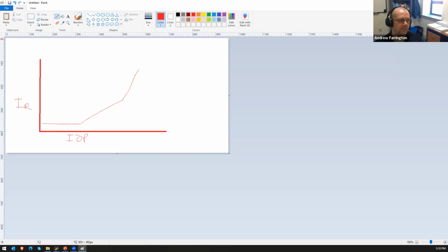Did that answer more or less what you were looking for, Paul? Yeah, it's just getting a bunch of points so that you're right below the curve and right above the curve. Oh, I see what you're saying. Yeah, to make sure the relay actually operates and restrains as it's designed.